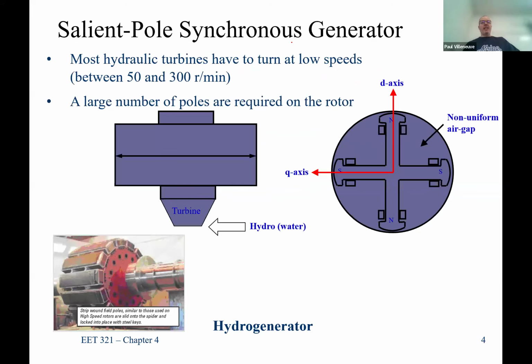There are 2 types: salient pole or round rotor. A salient pole is the one we talked about - you take individual magnetic material stamped out of a piece of iron, line them up, bolt them on each end, compress it, and hold it in place. That allows us to put a lot more poles. Each of these poles is concentrated in one area, and then we run the windings inside these areas - just a simple pictorial view.